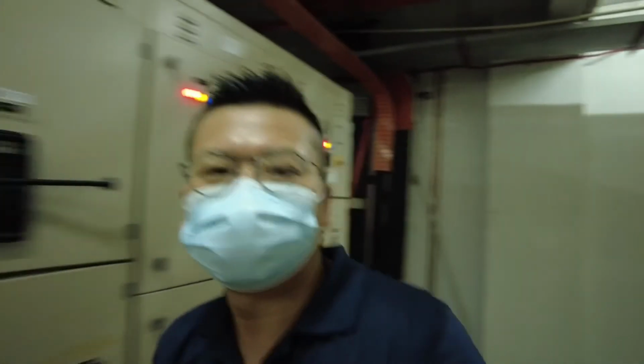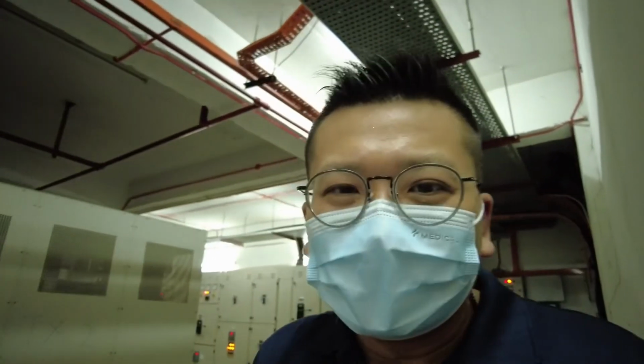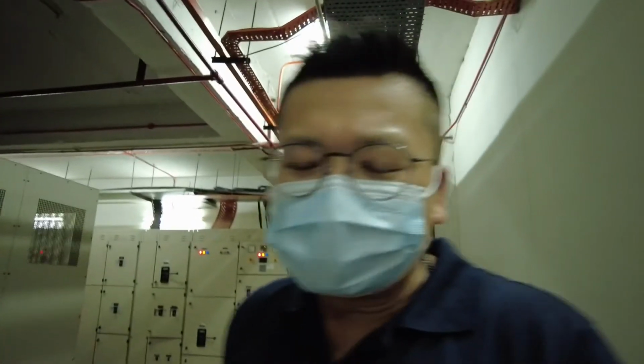I've just tested 3 units of genset at this shopping center, without going into the genset room to operate the genset to run. I just test ran the genset by using the jump signal or by operating the UVR relay from the ATS panel. Using this method, you can test whether your genset can run automatically and off automatically or not.